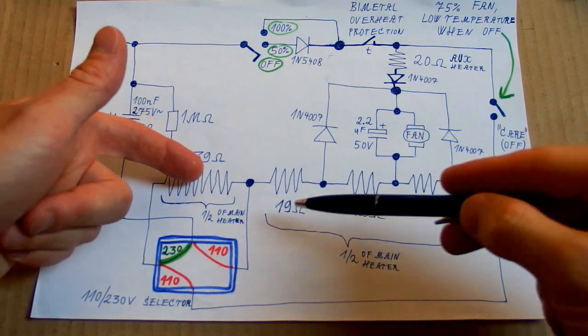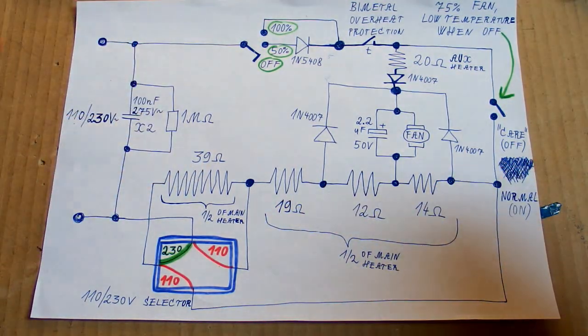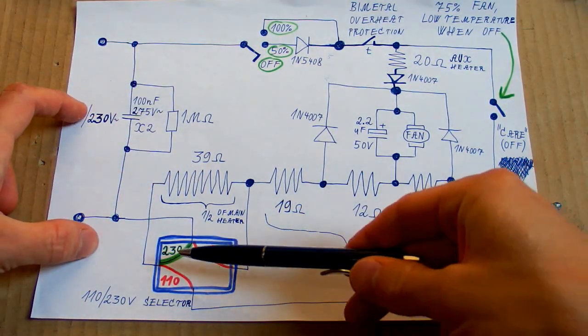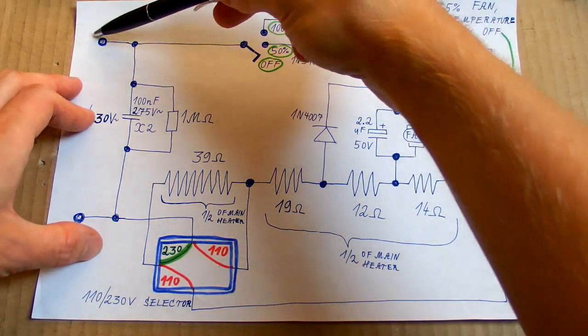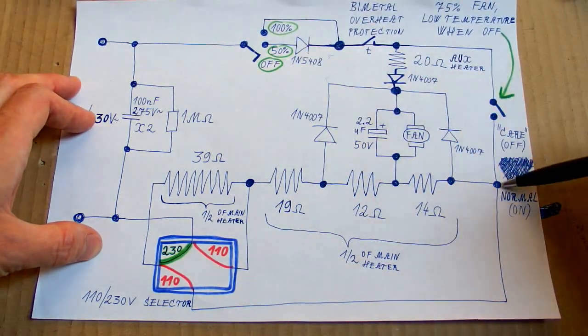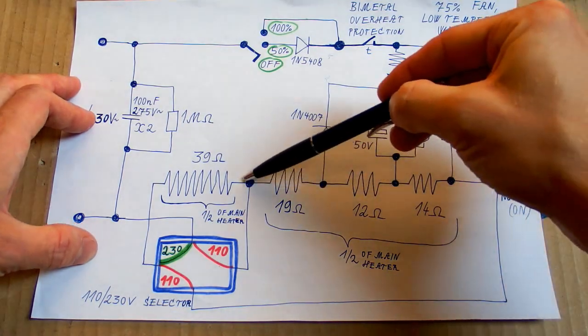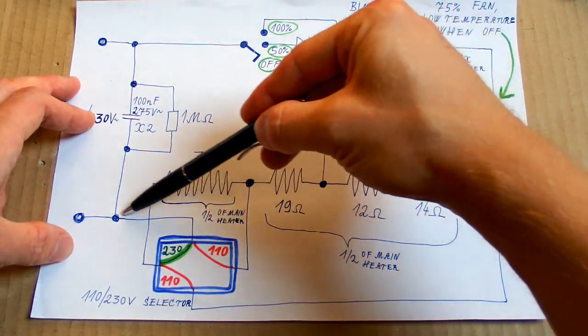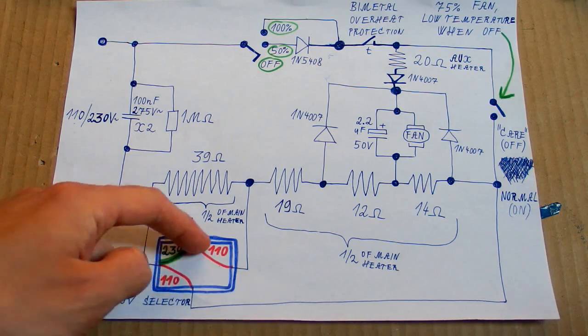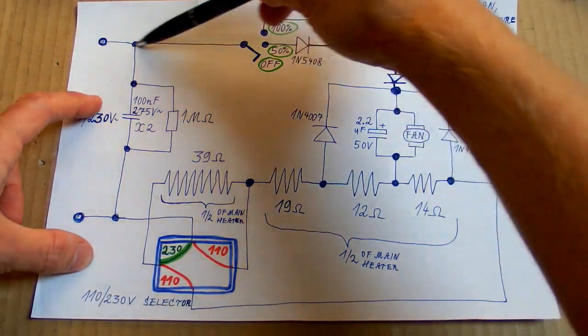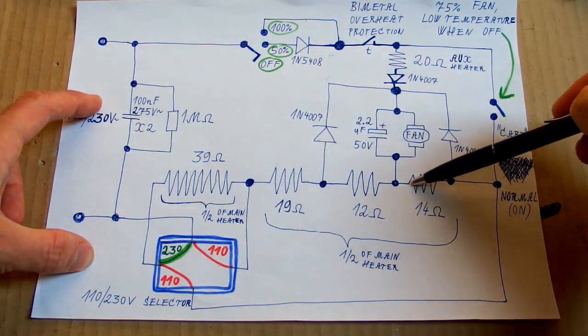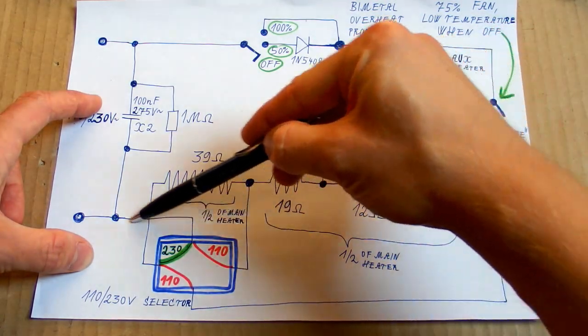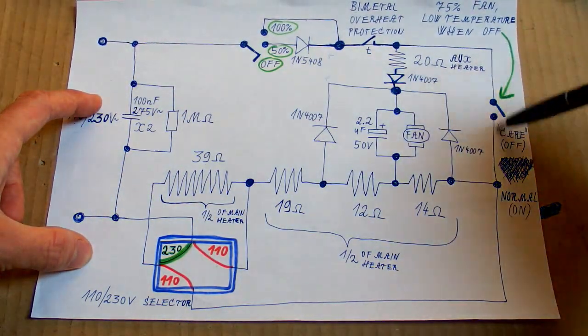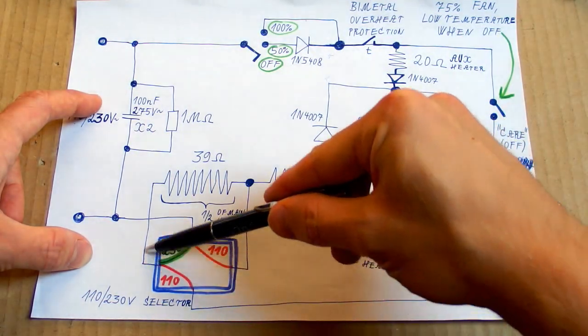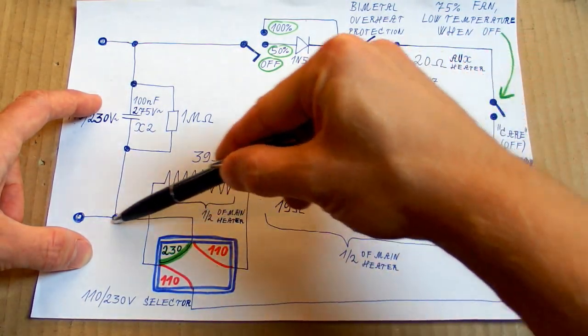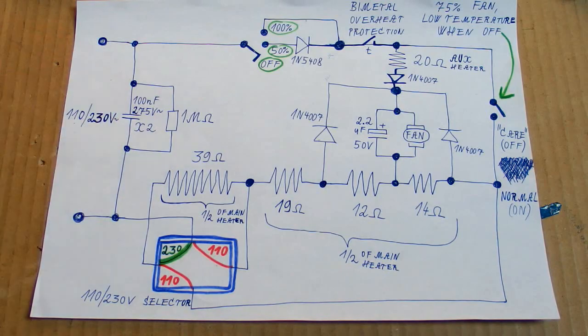Those two halves can be either in series or in parallel according to the mains voltage. For the higher voltages, it's all in series and the current goes via all of them in series like this and back. For the lower voltages, it's in parallel, so the power goes via one section and back, and also via the other section and back. So now they are in parallel.